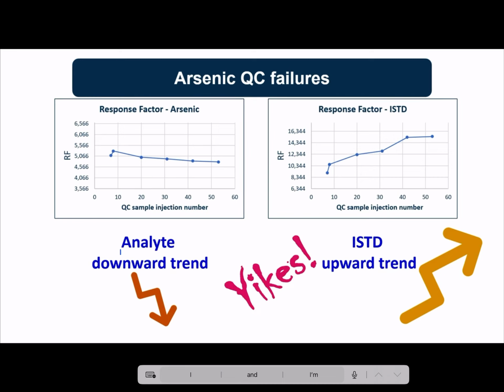Okay, it's not good to have opposite trending between your analyte and your internal standard. Typically, this was the first time that the internal standard was actually looked at. This was the first time that he realized that potentially the internal standard was an issue, and potentially a really large issue.